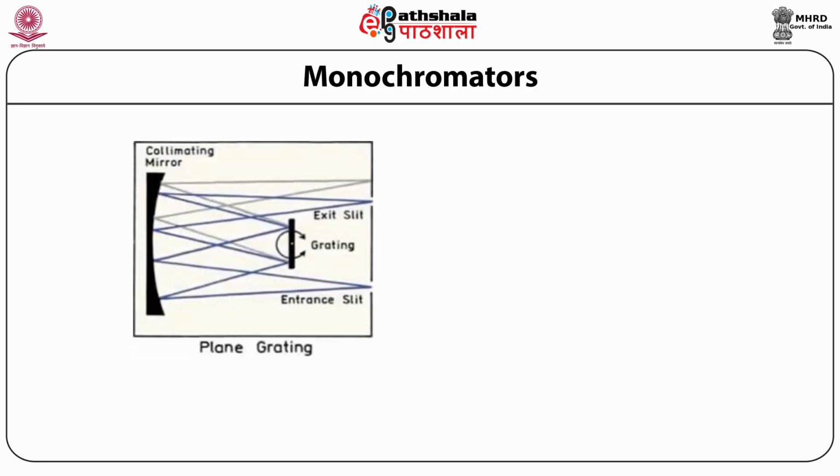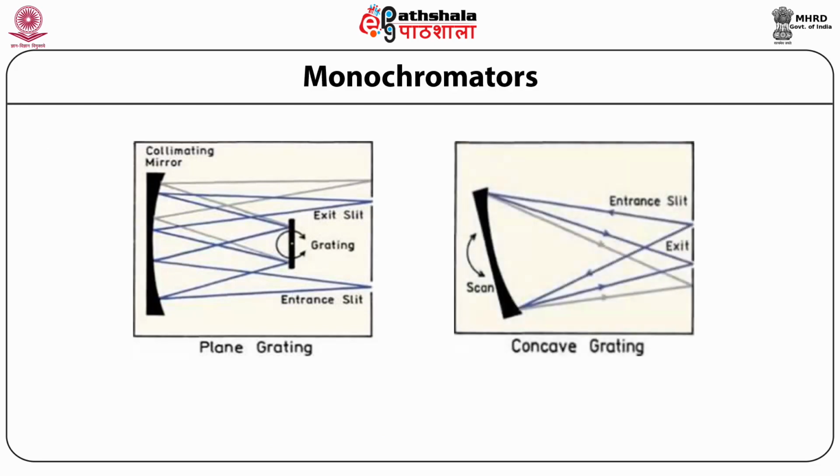The monochromators can have planar or concave gratings. Planar gratings are produced mechanically, whereas concave gratings are produced by holographic and photoresist methods. The stray light transmission and ghost images are due to imperfection of the gratings. So monochromators with concave gratings are more efficient and have fewer reflecting surfaces, therefore lower stray light. Holographic gratings are preferable for fluorescence spectroscopy for the same reason.